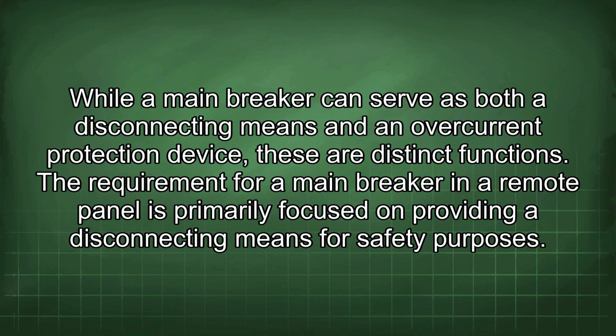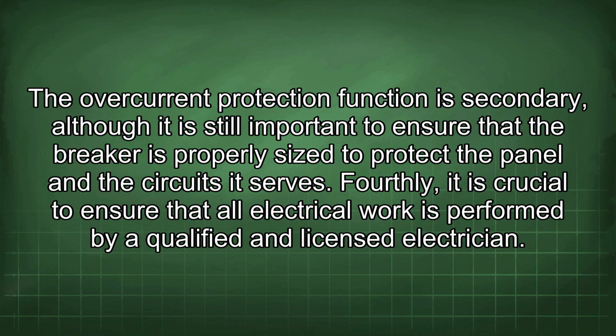The requirement for a main breaker in a remote panel is primarily focused on providing a disconnecting means for safety purposes. The overcurrent protection function is secondary, although it is still important to ensure that the breaker is properly sized to protect the panel and the circuits it serves.